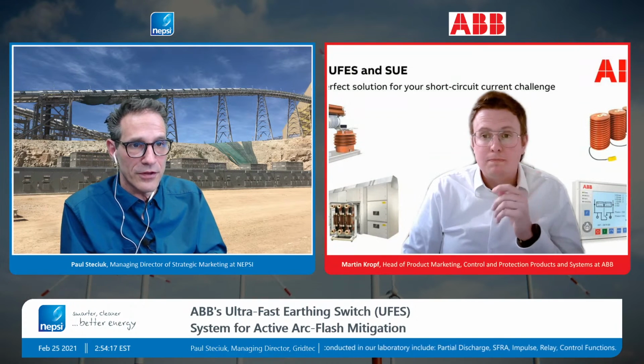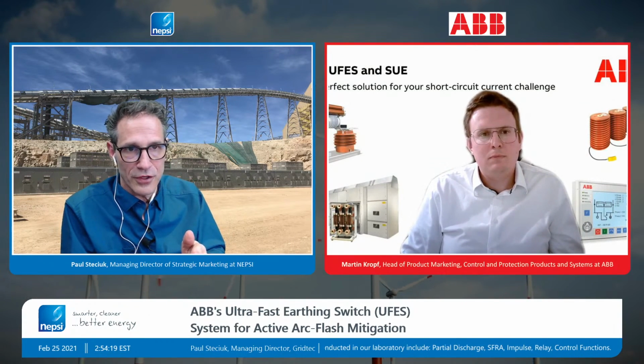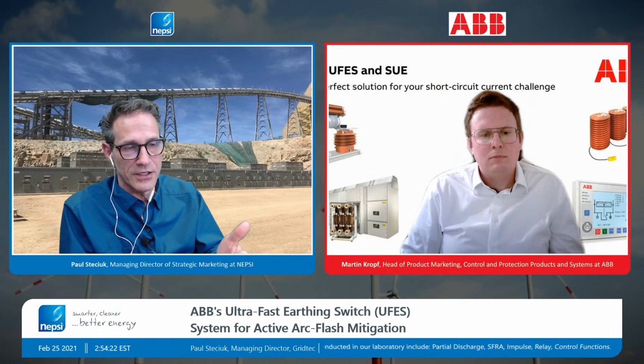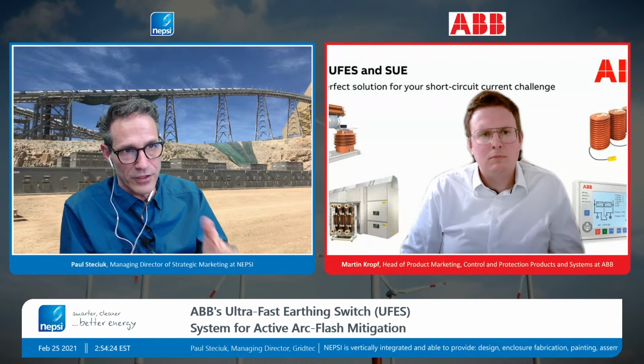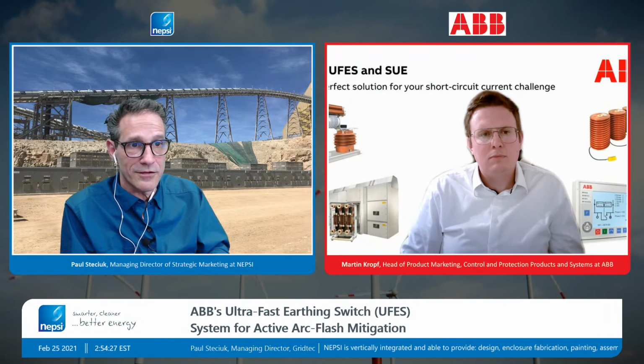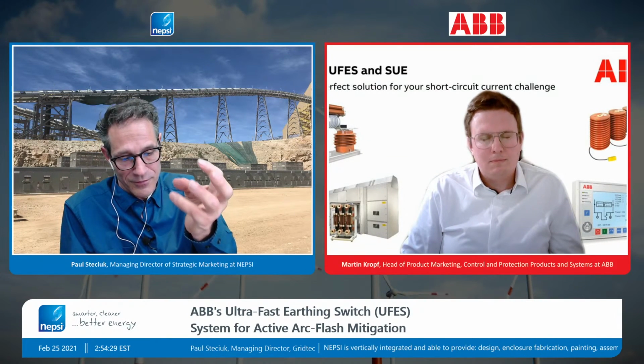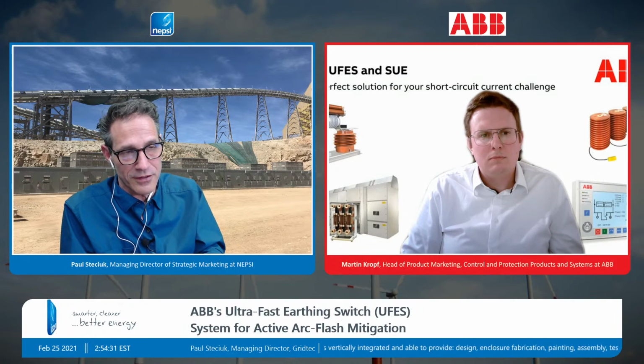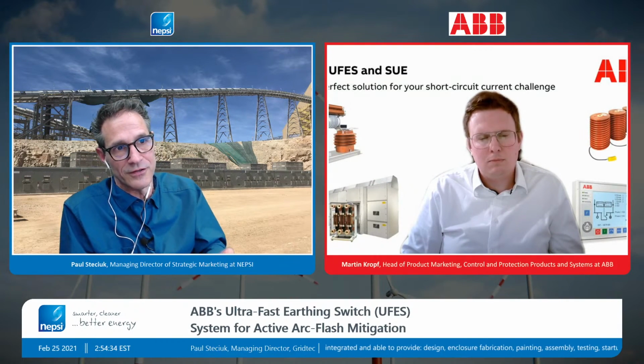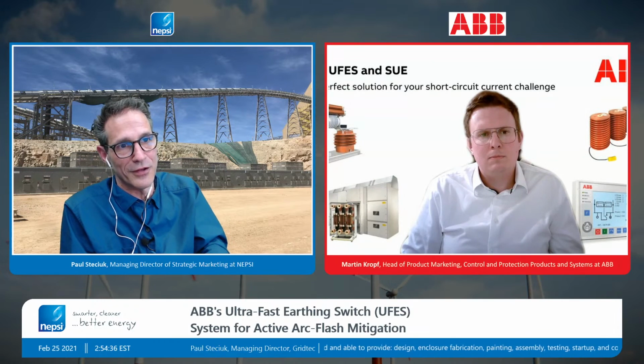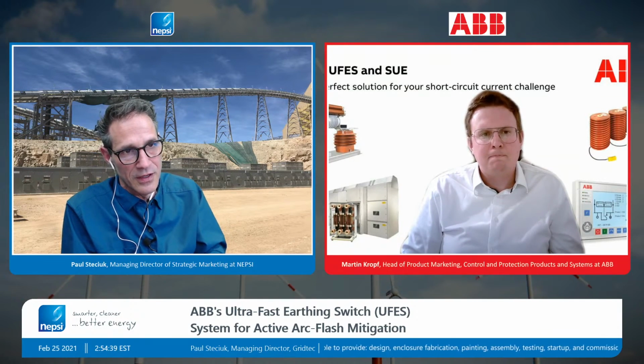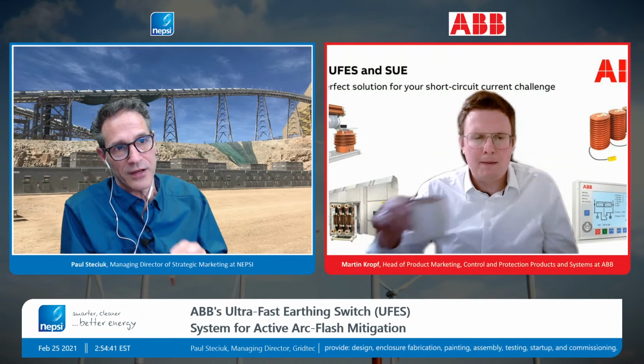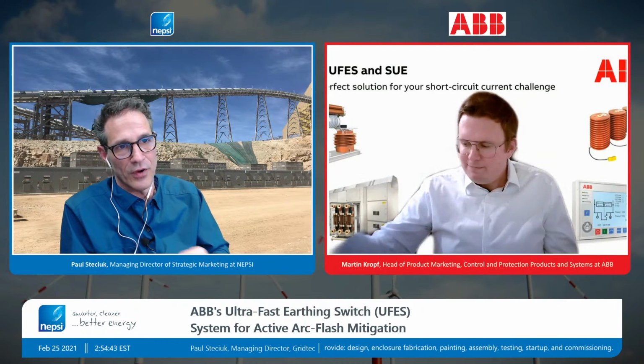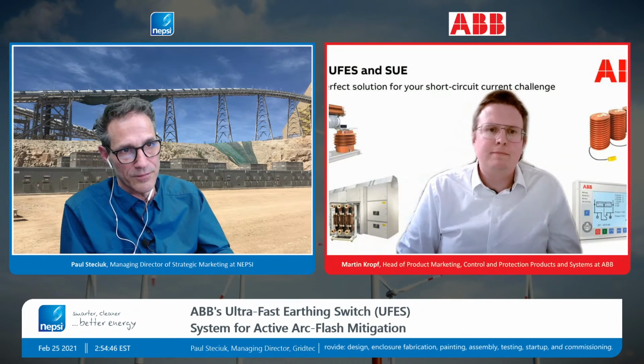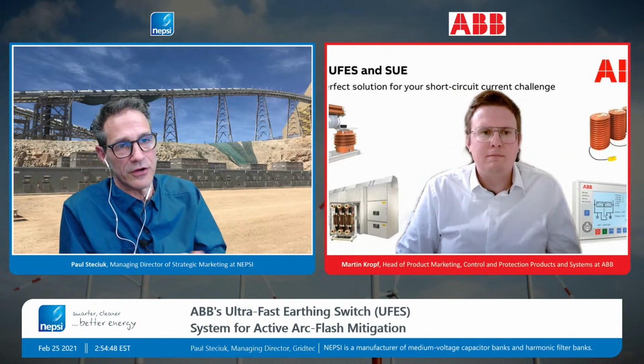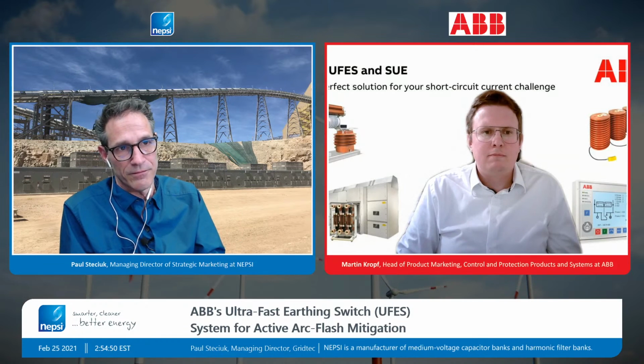During the period of time that you have an arc, that's when you have heat and pressure buildup. The heat and the pressure buildup is from the arcing event. In 4 milliseconds, Martin, correct me if I'm wrong, the UFES will shunt out that arc and the arc will disappear. Why? Because there's a zero impedance shunt around the arc and you eliminated the arc. Basically we're distributing the energy back into the source impedance rather than into the enclosure through the arcing, the heat associated with the arc. So it's not really dependent upon the upstream breaker.